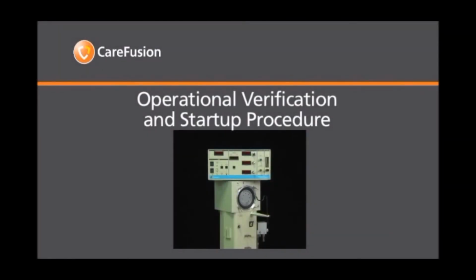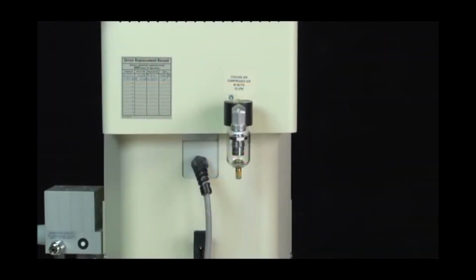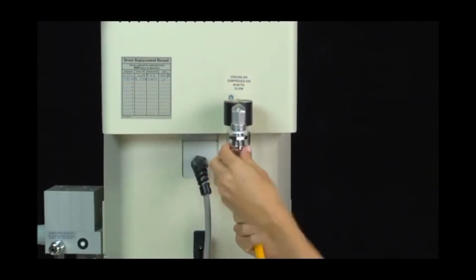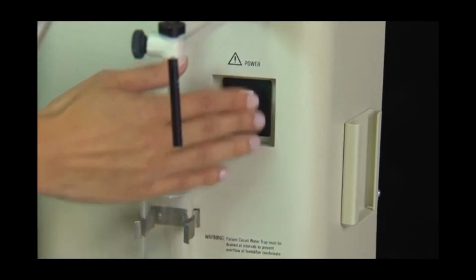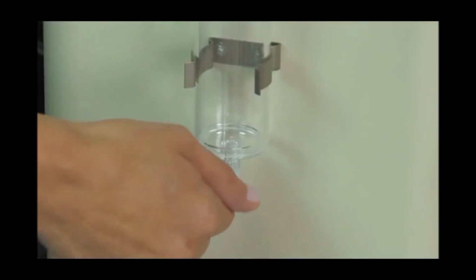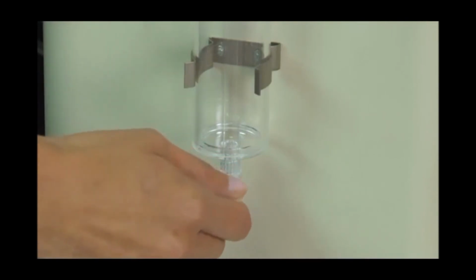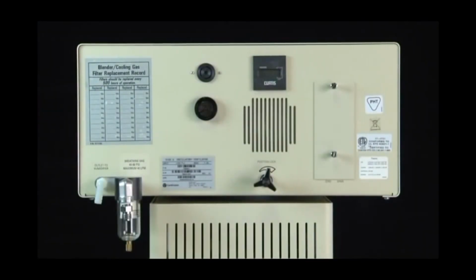The 3100A high-frequency oscillatory ventilator is now ready for the operational verification and startup procedure. The operational verification and startup procedure must be performed before using the ventilator. If the 3100A fails any part of this procedure, contact CareFusion Technical Support. Connect all source gases to the ventilator and turn on the main power switch. Ensure that the stopcock to the water trap is closed and the cooling fan at the rear of the driver enclosure is operational and clear of obstruction.